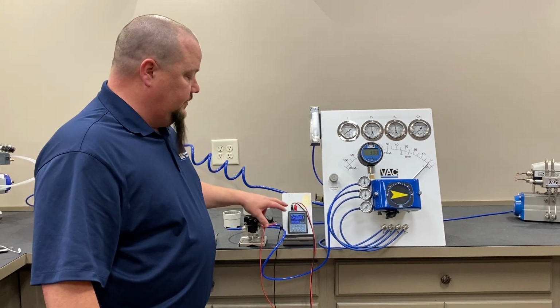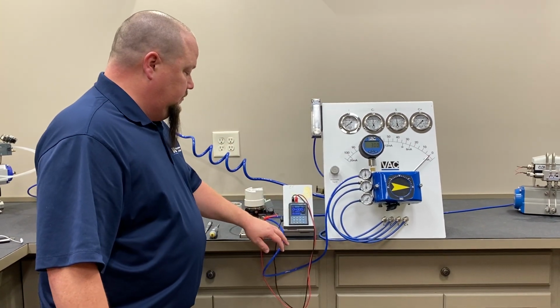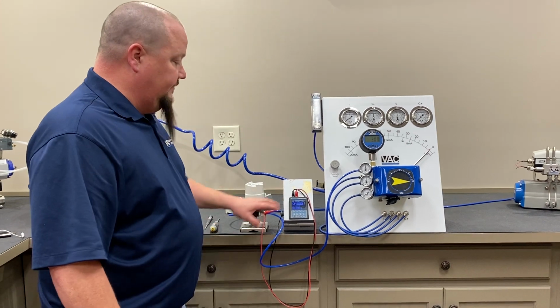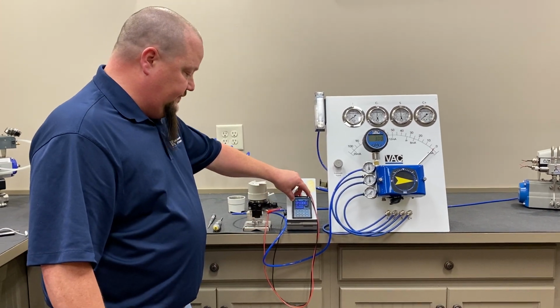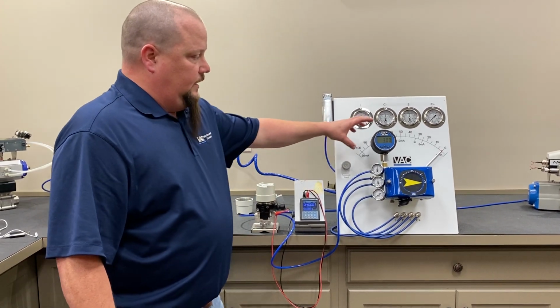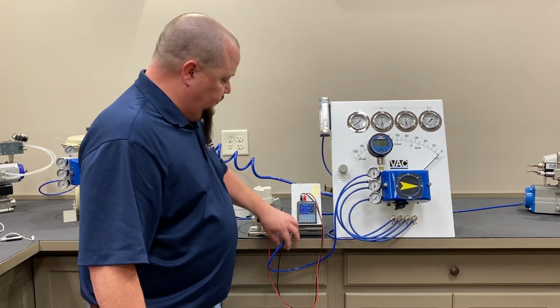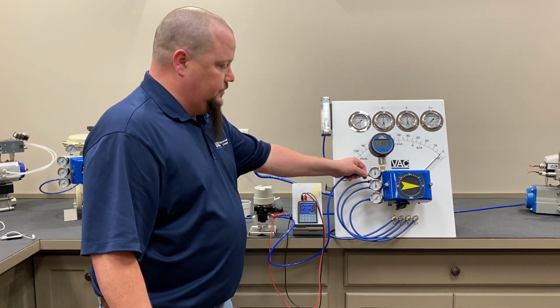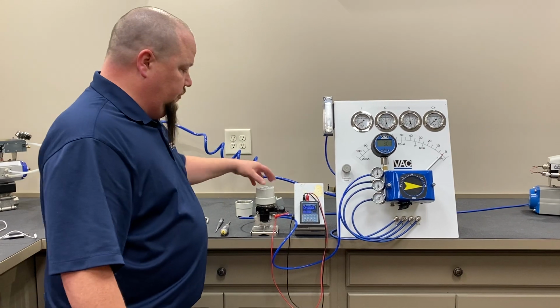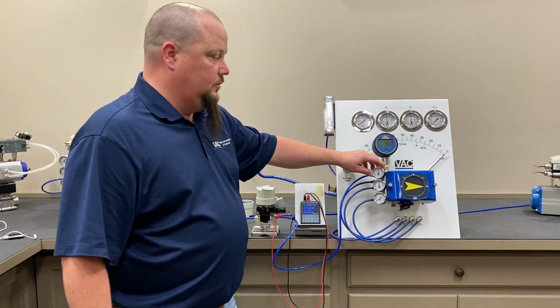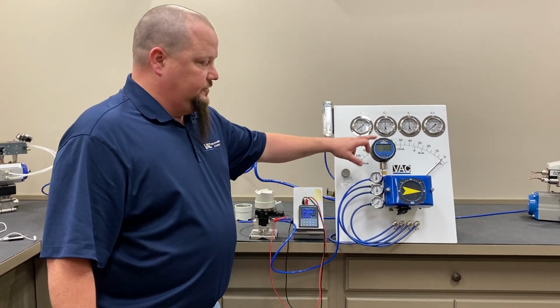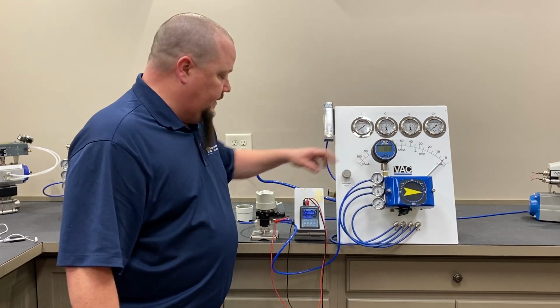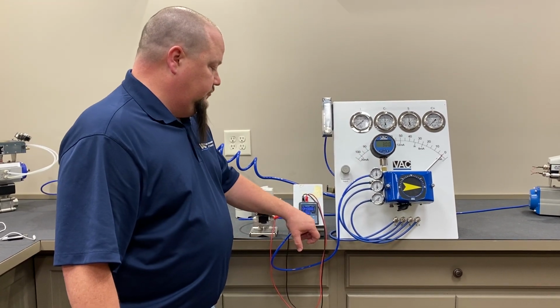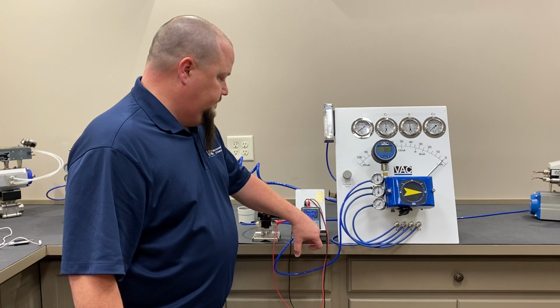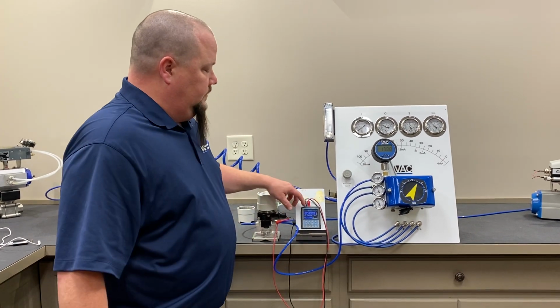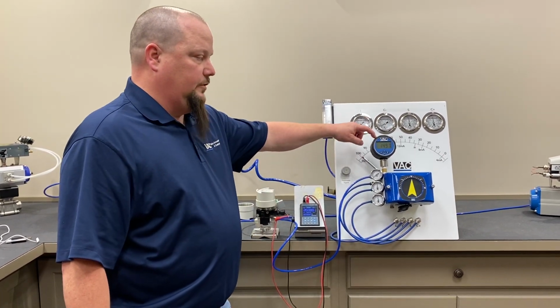On this unit I'm using a little signal generator we have. It is supplying 24 volt and 4 to 20 milliamp. And if you look at the gauge, this is tubed up to the I port on the positioner, as you would if you're using a remote mount I/P with a pneumatic unit. At 4 milliamps, you'll see that we have 3 PSI on our I port. And as we go to 20 milliamps, you'll see that we have 15 PSI on our unit.